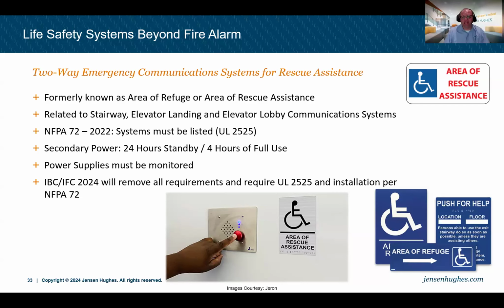All systems must have secondary power. That's 24 hours of standby and 4 hours of full use. Very, very similar to a fire alarm system. The power supplies must be monitored. And there are some other requirements, particularly when it comes to wiring. As of today, as of the 2024 IBC, the systems will need to be UL 2525 listed, and the installation will be per NFPA 72.